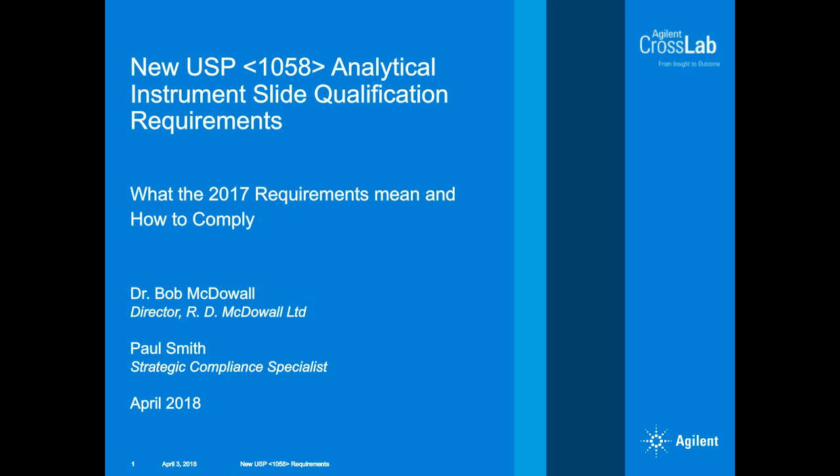And again, if you have 5 or 10 of the same pieces of equipment, don't write a user requirement specification for them all. If they all work to the same spec, you can just have one URS to cover all of those items of equipment. If it changes, then you've got a problem. You need to update the URS.